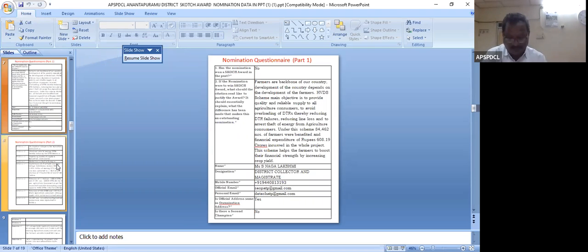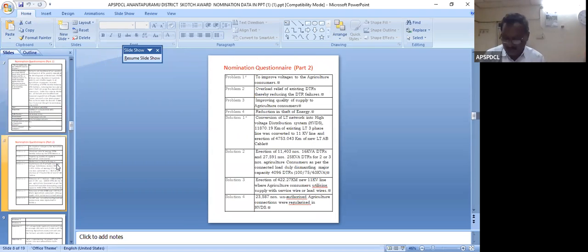Next. Here, sir, by the HVDS system we have converted 11,870.19 km of existing LT three-phase line into 11 kV line. We also removed the bare conductor and re-erected 4,753 km of LT AB cables. Instead of bare conductor, we used LT air bunched cables, sir.